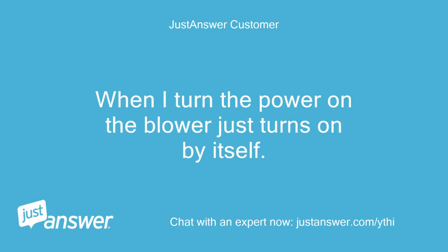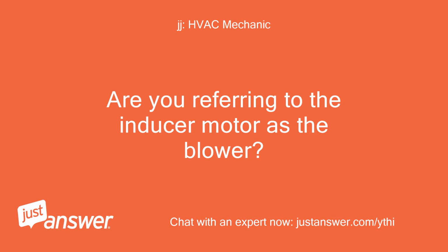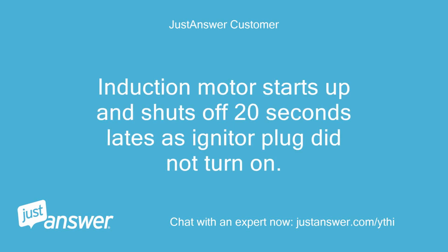When I turn the power on, the blower just turns on by itself. I refer to the blower as the big squirrel cage that moves the air through the house. Are you referring to the inducer motor as the blower? I need clarification. Large blower motor, squirrel cage, runs continuously. The induction motor starts up and shuts off after 20 seconds, as the igniter plug did not turn on.